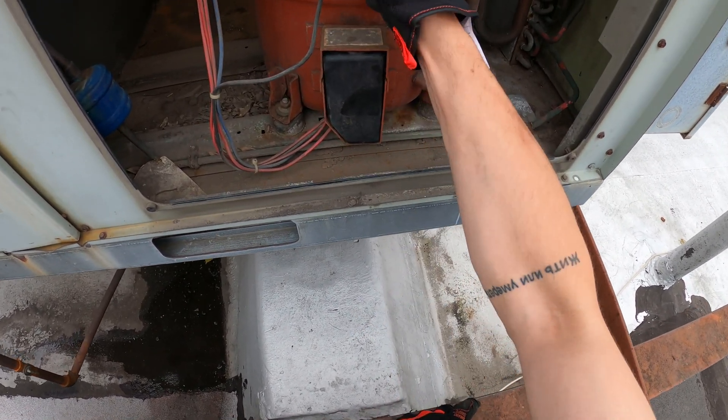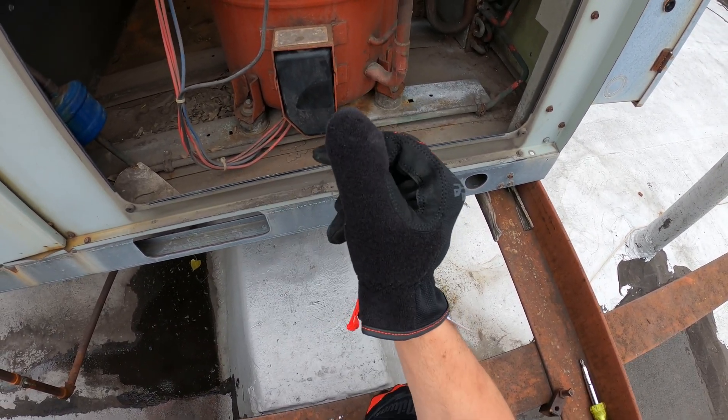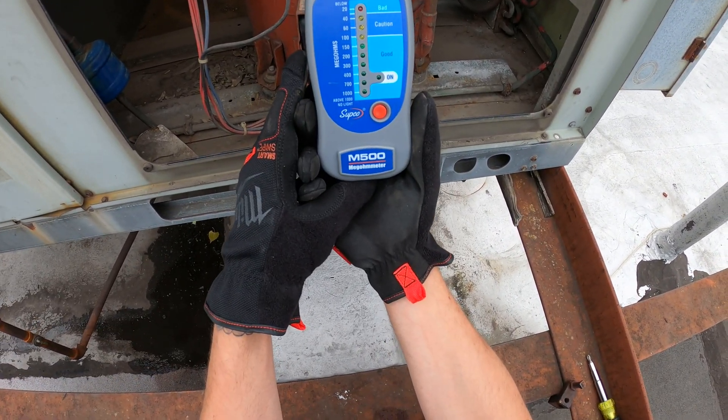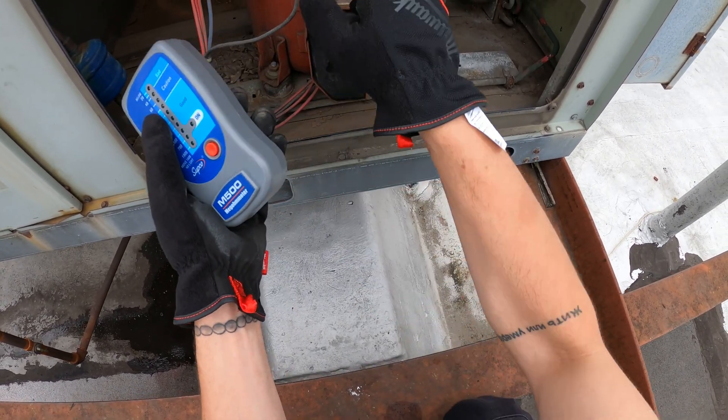Since it's running on high pressure, most likely this compressor is running hot. And when the compressor runs hot, you start losing the insulation in your windings. So what we're going to do today is use the M500 Megohmmeter and do an insulation test for the compressor.